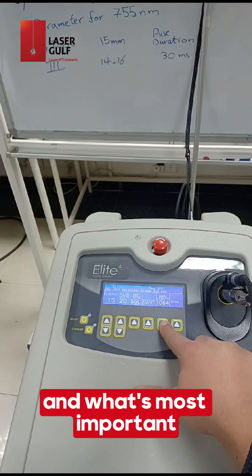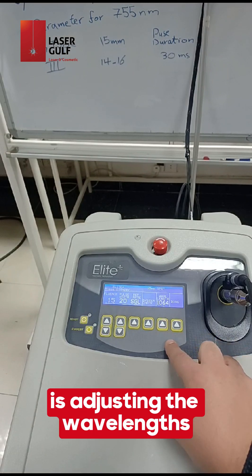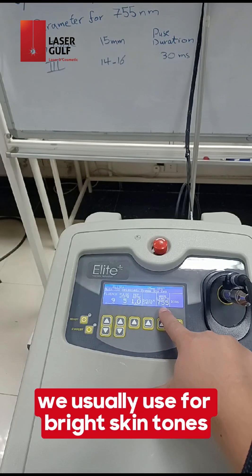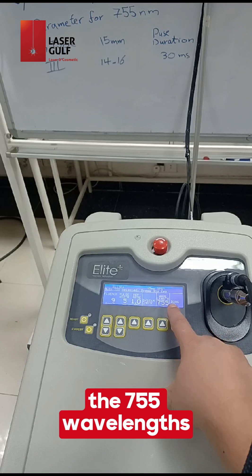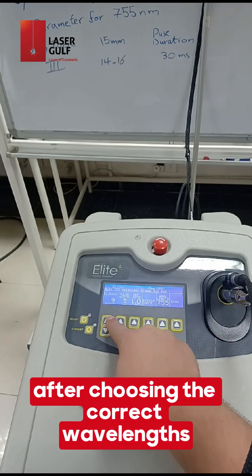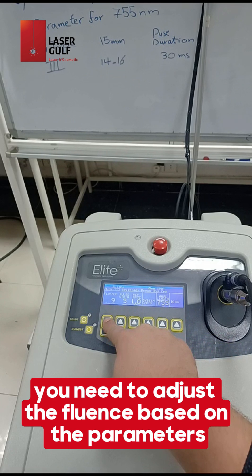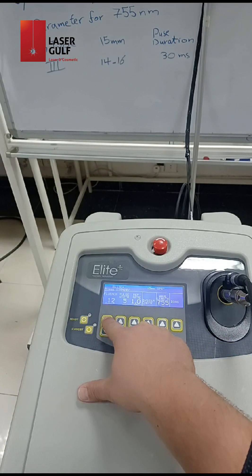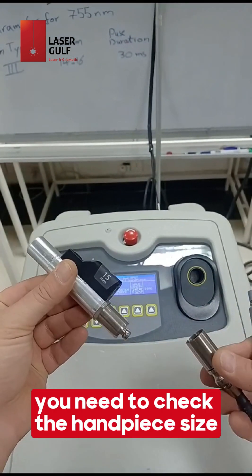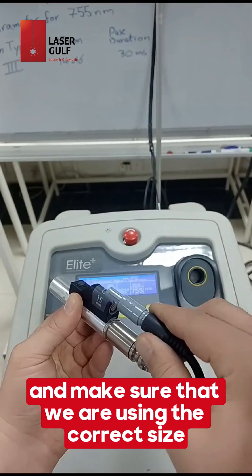When setting up a treatment session, first and most important is adjusting the wavelength based on the skin tone being treated. We usually use the 755 wavelength for bright skin tones and the 1064 wavelength for darker skin tones. After choosing the correct wavelength, adjust the fluence based on the parameters and the patient's skin tone. Then check the handpiece size and make sure you are using the correct size.